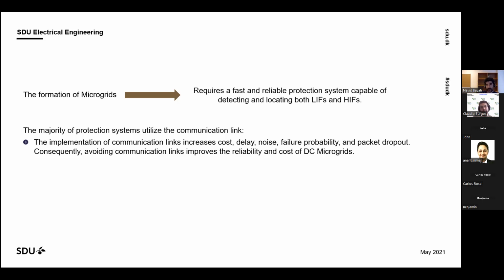But if we are talking about the power system, normally we have around 5 or 6 cycles to remove the faults based on a standard, and if we have huge inertia, we can extend that sometimes to 10 cycles, so around 200 milliseconds. But in microgrids, right now we don't have too many standards. Because the rate of change of the current is very high, we should detect, locate, and isolate the fault very fast, in less than a couple of milliseconds.